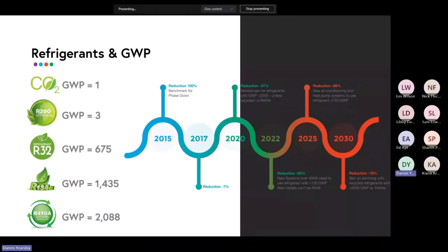And the refrigerants have an environmental score which we call GWP, global warming potential. It's basically the amount of damage which gets done to the environment if you let off a kilo of gas, and they give it a score. The gold standard currently is CO2, which has a GWP of 1, which means it's basically inert. You can let the CO2 off and it doesn't do any greenhouse damage, so no warming effect with it.